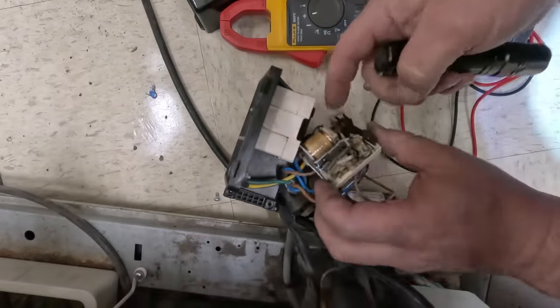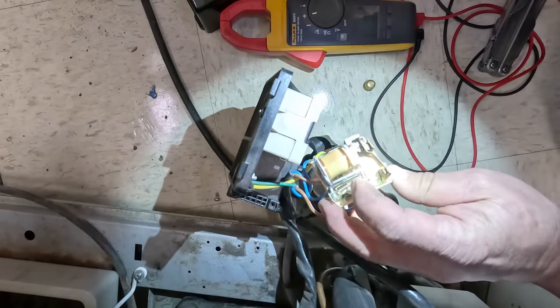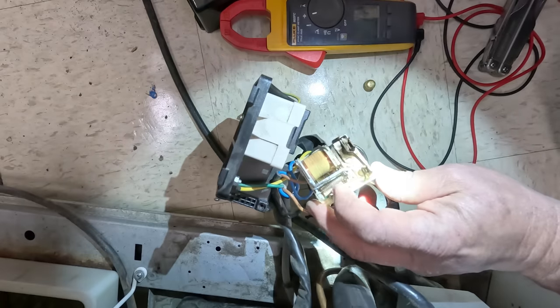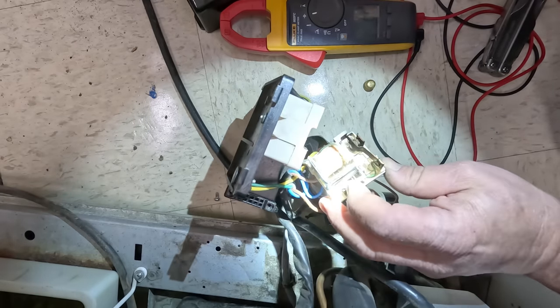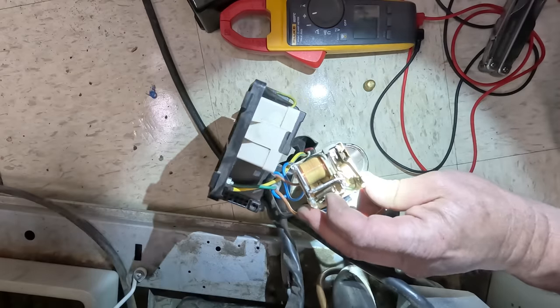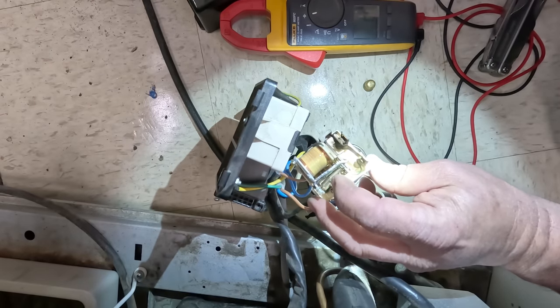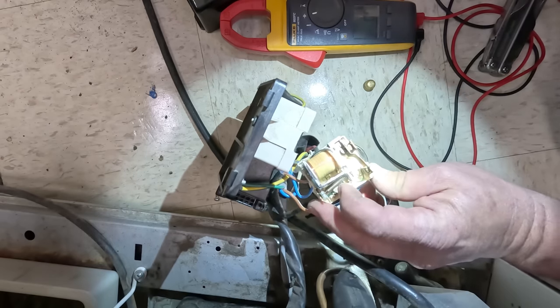Definitely not in good shape. The main thing is you need that to be closed so the capacitor is in the circuit. Then when the back EMF from the compressor gets high enough, it'll make this coil energize, breaking the start capacitor out of the circuit, which then lets the compressor run without the start capacitor in the circuit — and the run winding continues to do its job.